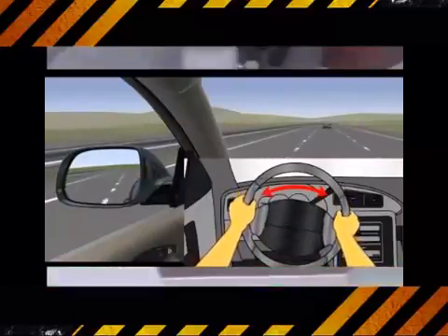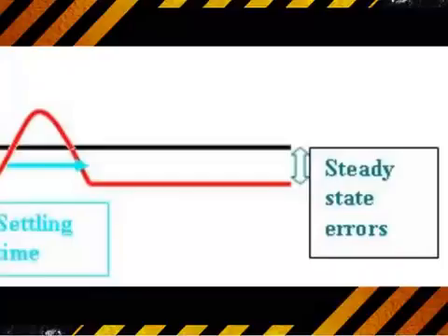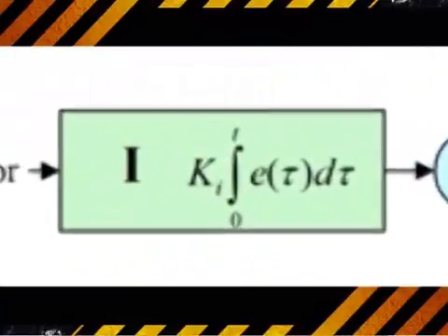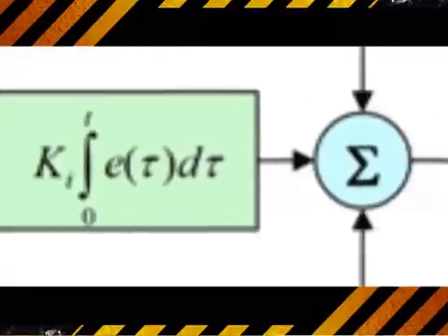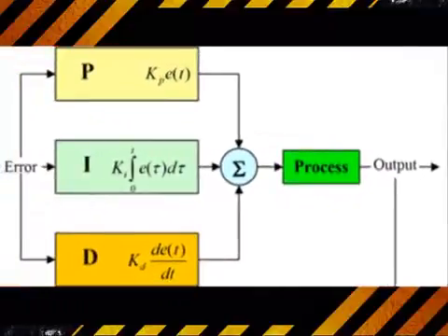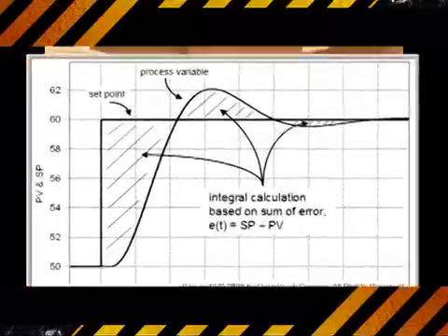This is where the integral action is used to overcome the deficiencies of proportional action. Proportional action is simply the P gain multiplied by the error. If the error is holding constant, but you aren't at your target set point yet, you will be stuck. This is called an offset, and is the problem with P-only control. The addition of integral action overcomes this deficiency. If there is an error between the set point and the process variable, integral action will start to ramp up the controller output until things start moving again. Mathematically, it increases the controller output by the integral of the error.